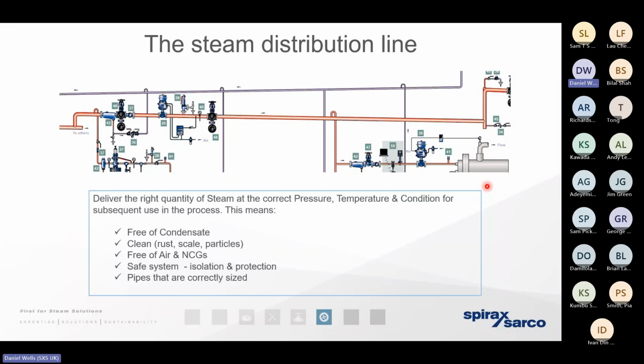So when we're talking about a good condition of steam, we're talking about plant steam here. We're not talking about steam for critical applications like food and beverage or pharmaceutical applications where the steam could come into contact with that product and therefore would need to be considered an ingredient. So when we're talking about plant steam as a utility, we're typically talking about keeping it in a good condition, which means keeping it as dry as we can. We do that by getting rid of as much of the condensate as we possibly can across those steam traps. Keeping it free of any rust or scale or particulate that could result in erosion or blocked orifices of steam traps and control valves. We need to vent away air and any other non-condensable gases.